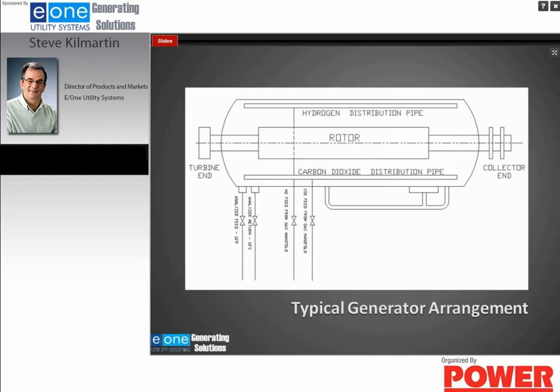Now, you will note that if I was still taking my sample where I take it during my normal operation, as soon as I start to put carbon dioxide in this, because those points are at the bottom of the generator, they're going to see carbon dioxide immediately, even though the top half of this generator's got air in it. So it's very important where you're taking your sample from.